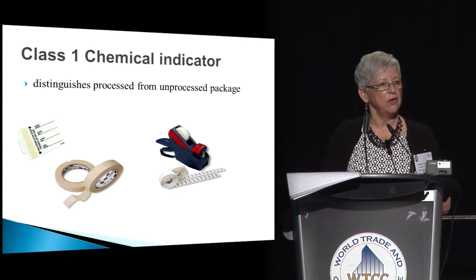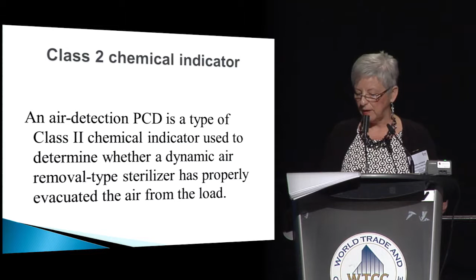So Class 2. A Class 2 chemical indicator is an air detection PCD. It's determined rather for air removal, the Bowie Dick. And on the next slide, you'll see the Bowie Dick tests, and these tests are performed daily when the sterilizers are being used, first thing in the morning, to make sure that all the steam has been pulled, all the air's been taken out of your sterilizer.